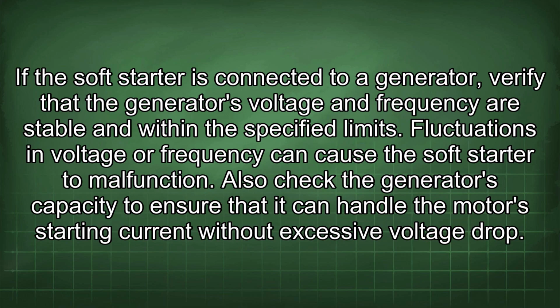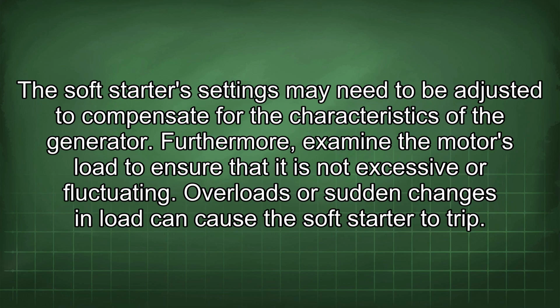If the soft starter is connected to a generator, verify that the generator's voltage and frequency are stable and within the specified limits. Fluctuations in voltage or frequency can cause the soft starter to malfunction. Also check the generator's capacity to ensure that it can handle the motor's starting current without excessive voltage drop. The soft starter settings may need to be adjusted to compensate for the characteristics of the generator.